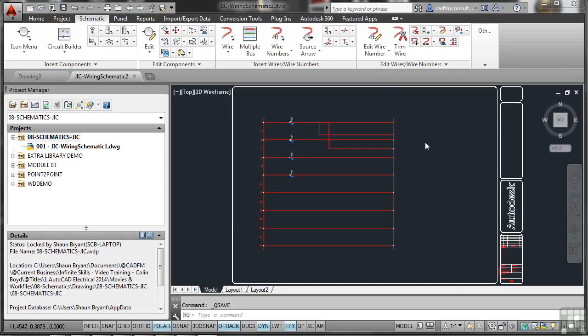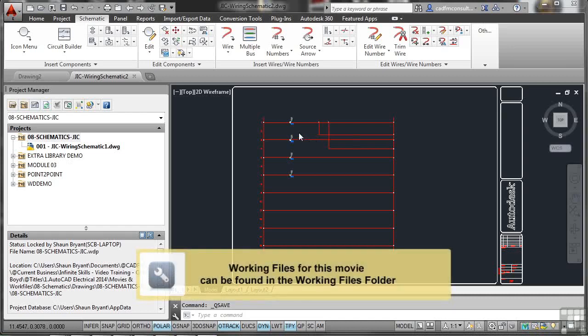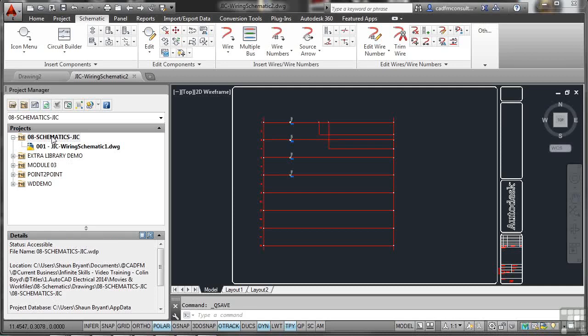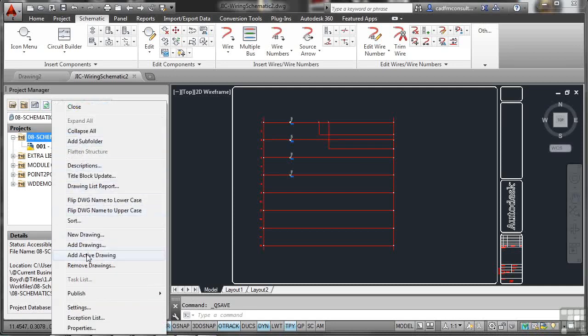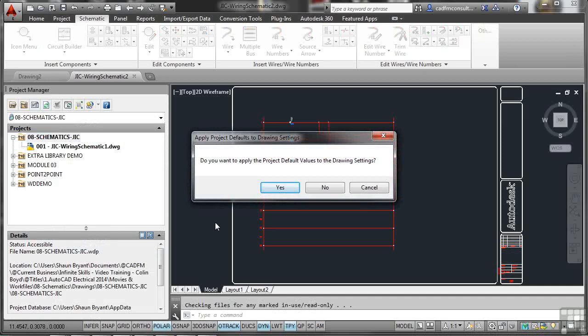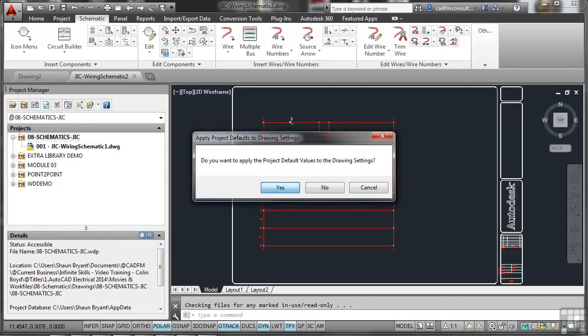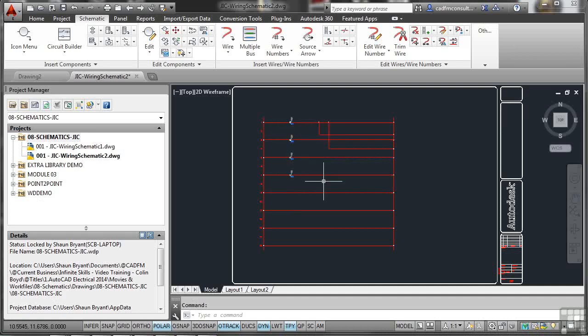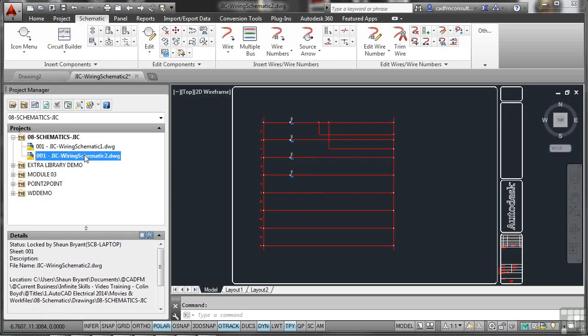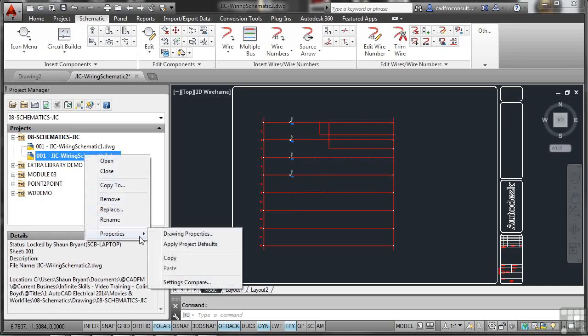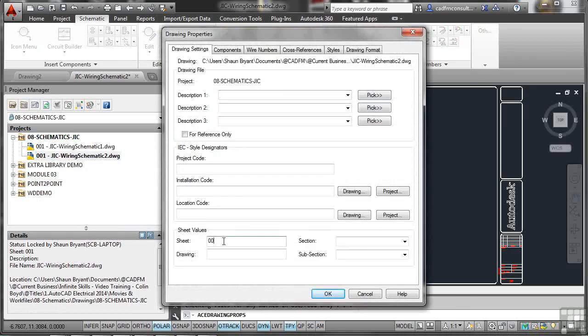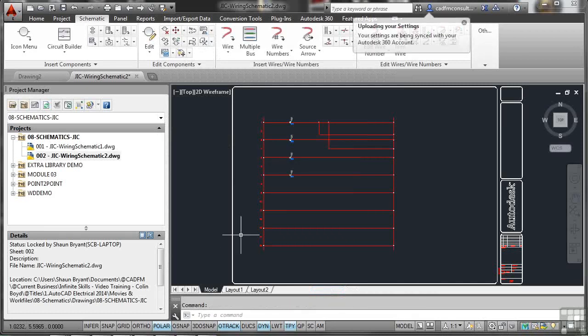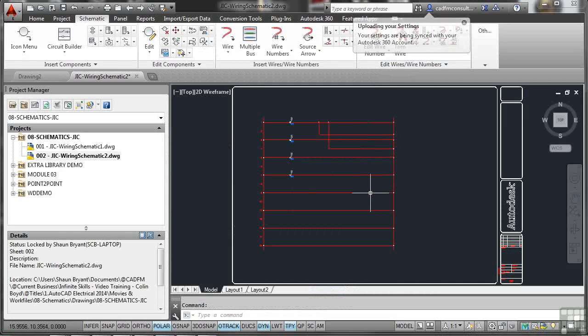OK, so we've now added our terminal connectors. They're there on the rungs of our ladder. What I've done here is I've done this deliberately. I've saved the drawing as another drawing. So, we're now J-I-C, Wiring Schematic 2. OK, now there's a reason I've done that, and you'll see why. When I go to the project, and I right-click and add the active drawing now, it'll ask me, do I want to apply the project default values to the drawing settings? Yes. And I'll update that. Now, what it's done there as well is it's automatically updated those in the database. So, it now knows that it's got eight terminal connectors because this might be a drawing of a different circuit. So, just be aware of that. So, what I'll do there now is I'll right-click, just sort out the properties, change that to sheet two so that we've got a proper numbering and naming structure there. And you'll notice again, 360 is updating and syncing in the background.